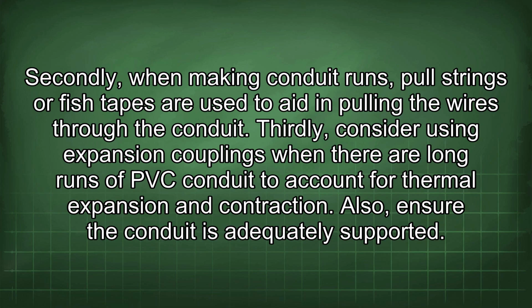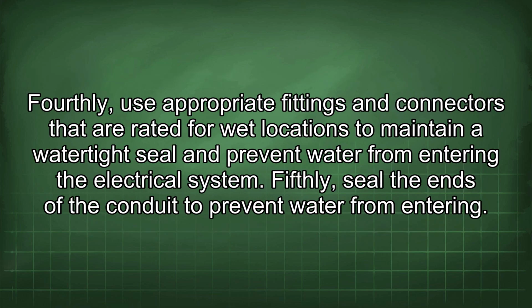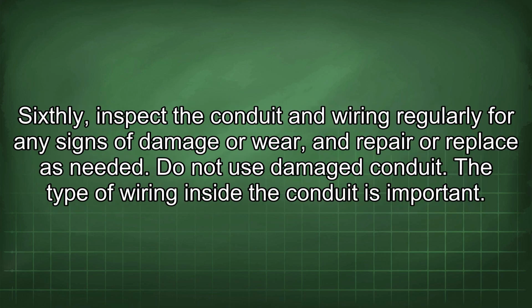Thirdly, consider using expansion couplings when there are long runs of PVC conduit to account for thermal expansion and contraction. Also, ensure the conduit is adequately supported. Fourthly, use appropriate fittings and connectors that are rated for wet locations to maintain a watertight seal and prevent water from entering the electrical system. Fifthly, seal the ends of the conduit to prevent water from entering. Sixthly, inspect the conduit and wiring regularly for any signs of damage or wear, and repair or replace as needed. Do not use damaged conduit.